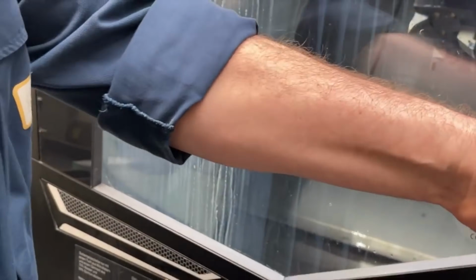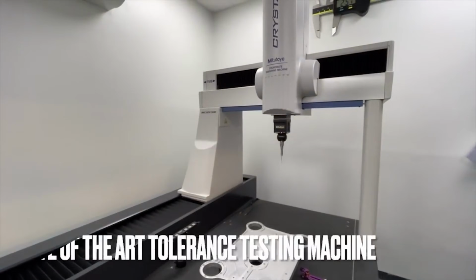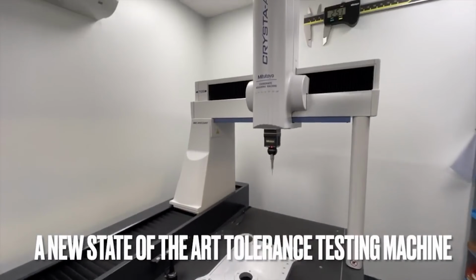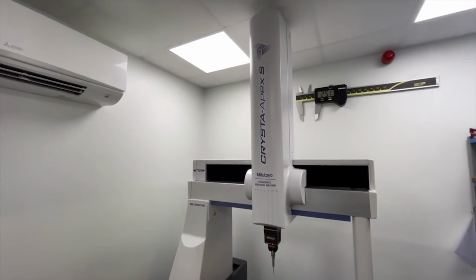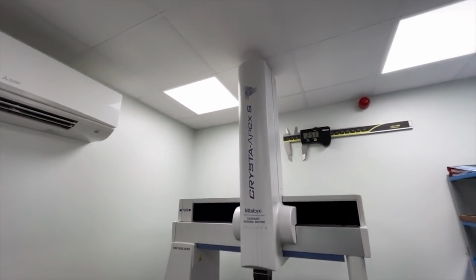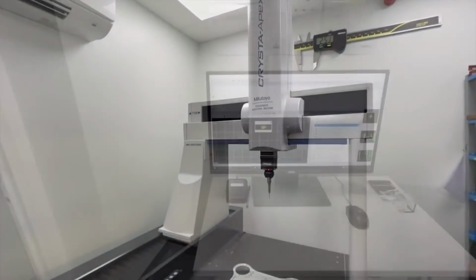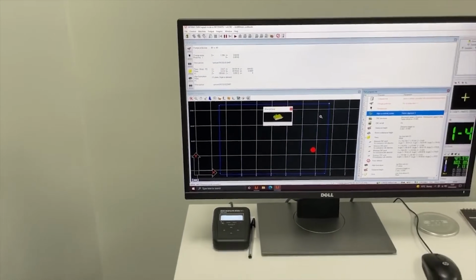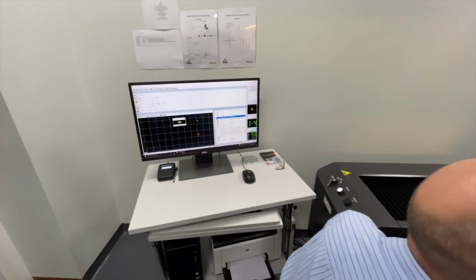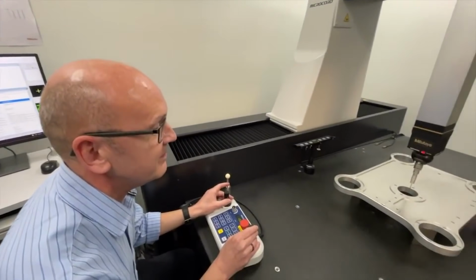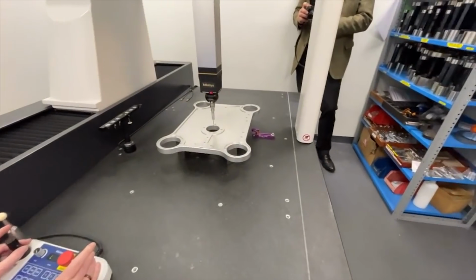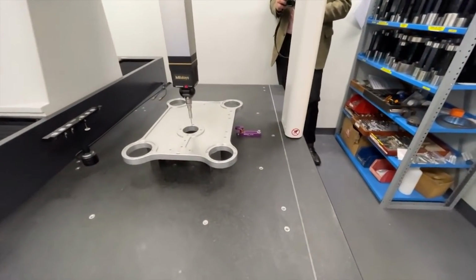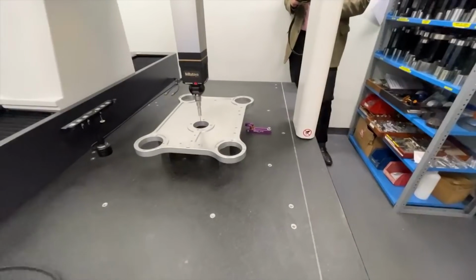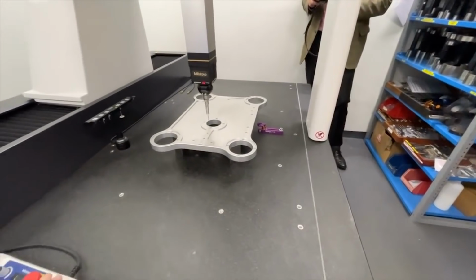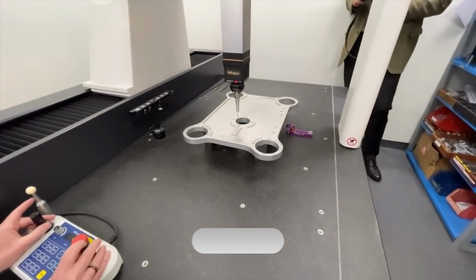So this is our coordinate measuring machine, solid granite bed, fully motorised head, 6 tool probes, thermally compensated. The origin now. 2. Now these are done manual at the moment, but we have got the facility that if we had multiple components we can do it automatically. Now, does every machined chassis have to be put into this machine? It will be, so that each one is checked. It will be, yes, certainly. Element finished.